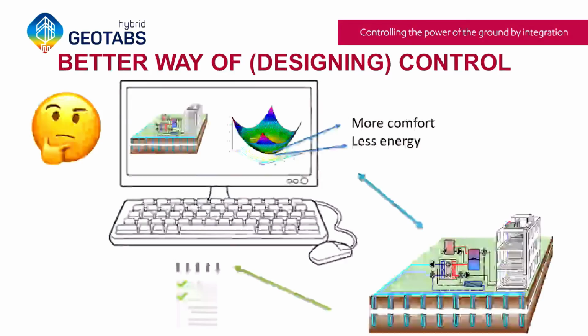So most probably the way of the future is not to define, by hand, all the different rules and interactions into software, but much more to create a software where we can give the general physics of the building, or which type of HVAC is present in the building and which type of building it is, which type of occupancy there is, which type of schedule, which type of internal gains are expected, and solar gains. We put this more physical information into the software, and the software automatically sets up which control signals need to be sent to the different machines, taking into account the connections between these different systems.